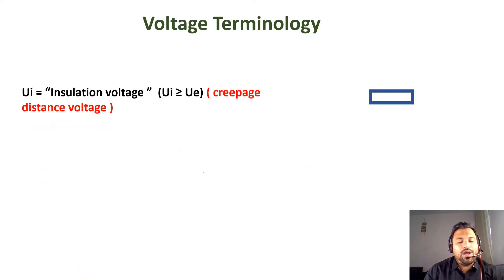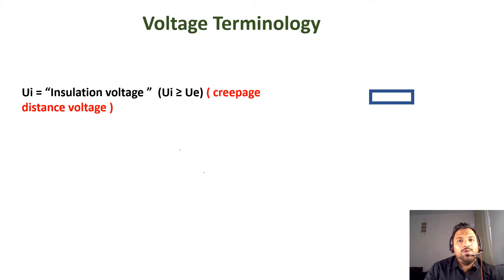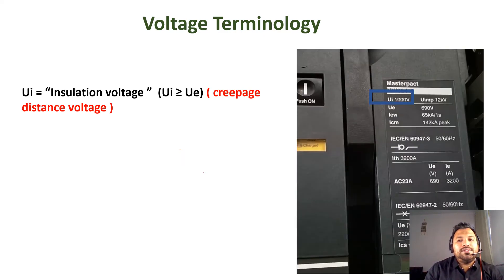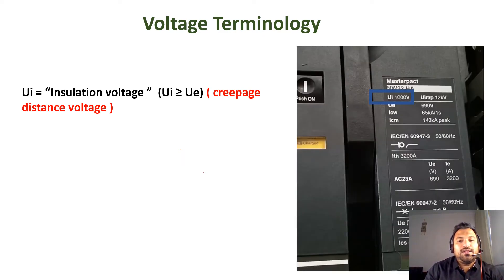The next terminology is Ui — the insulation voltage, also called creepage distance voltage. Basically, the Ui value is always greater than the operational voltage. On this circuit breaker, Ui is indicated as 1000 volts, while the operational voltage Ue is 690 volts. So Ui must always be greater than the operational voltage.